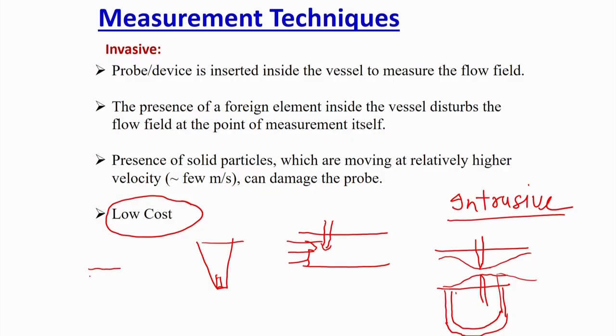We will also try to see some of these techniques for invasive multiphase flow measurement. The best example is the pitot tube. Cost-wise, it is nothing but a small tube connected with a manometer. I can add a pitot tube to a pipeline and it gives me the point velocity. It is very cheap and widely used. Though the velocity may change at the point of measurement itself, it is very accurate in single-phase flow, but in multiphase flow you will just get an idea.